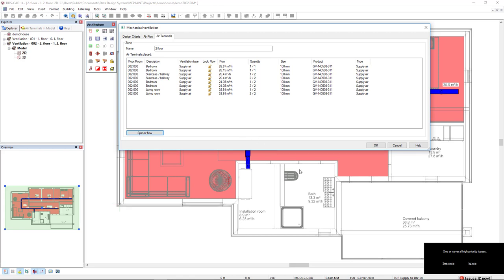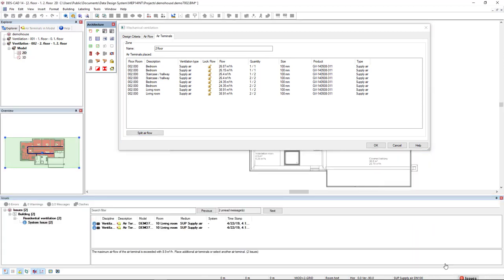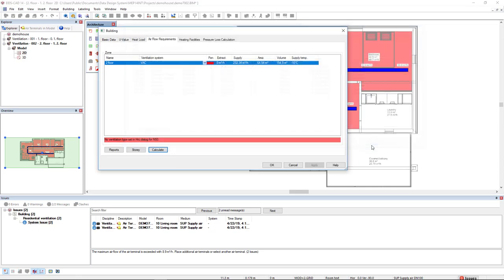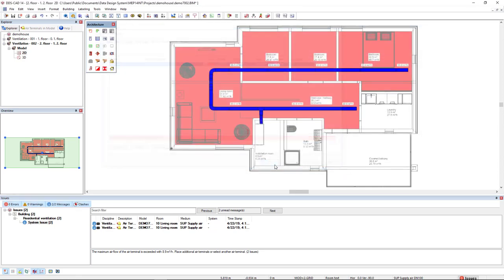We see that an issue has been added. If we click see more, we see that we have two air terminals that exceed the maximum of 330 cubic meters per hour. And they are in the living room as we can see here. Click OK. I'll click OK again. And I will refresh.